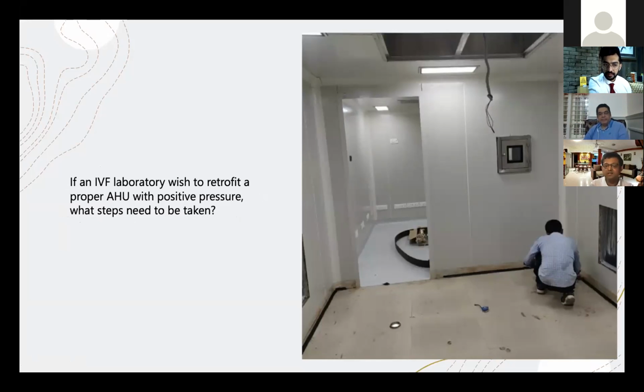And the second thing is whether both the culture room and OT are connected only through a small window through which one passes the tubes or petri dishes. Because remember, if everything else is made up of wall, and there is only a small window available which intermittently opens, there is absolutely no use having a single AHU fitted for your culture room, because that will never have any communication with the OT.